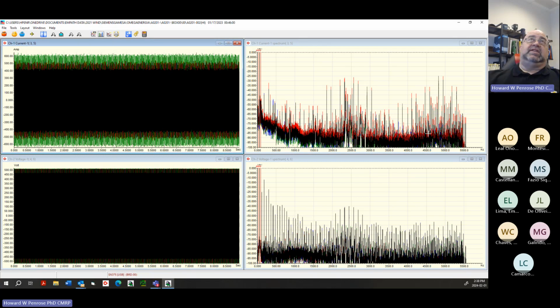Because it's 12,000 hertz, the Nyquist is actually 6 kilohertz - basically Nyquist of 2, so half. And 5,500 is the roll off. So any frequency from 0 to 5,500 with the system you have is good. Take that, multiply it by 60, and that'll give you the CPM if you're talking to a vibration analyst. Basically, there's nothing in the tower you won't be able to see with that data set.